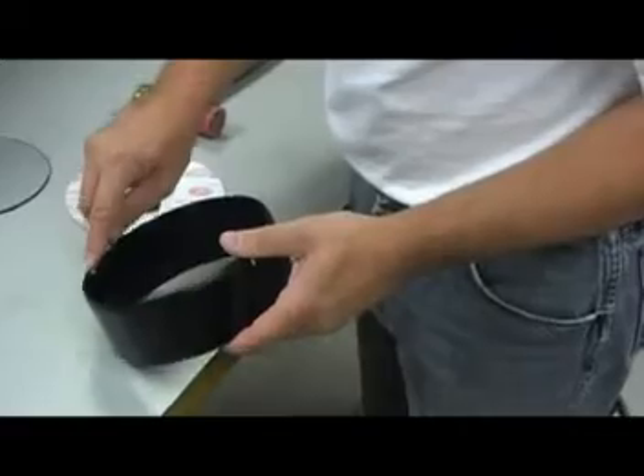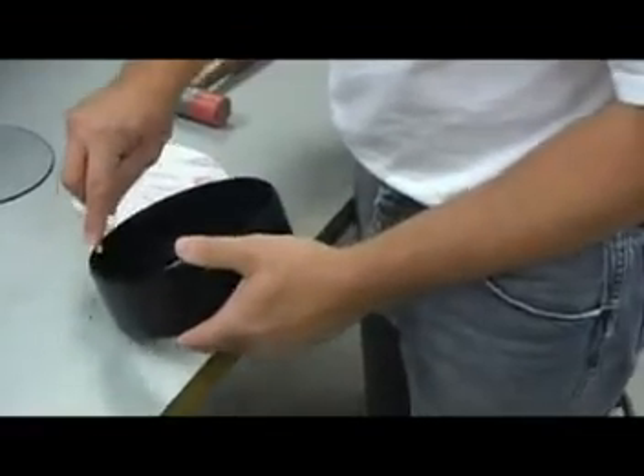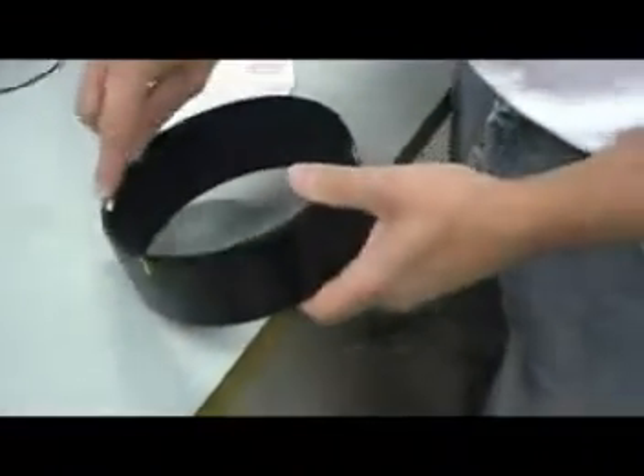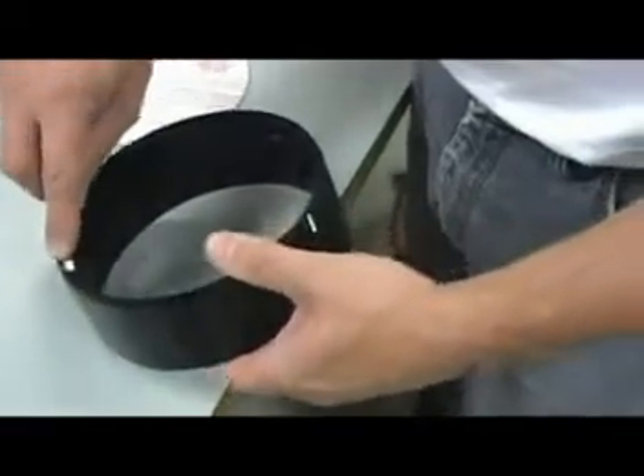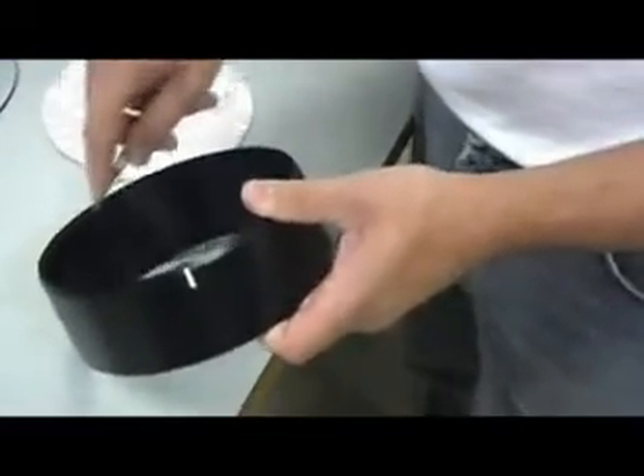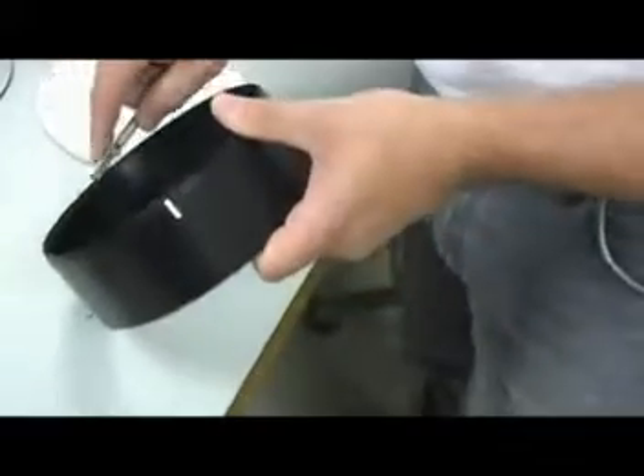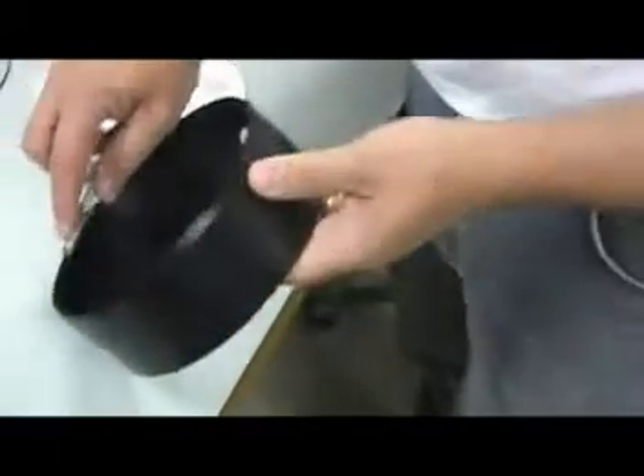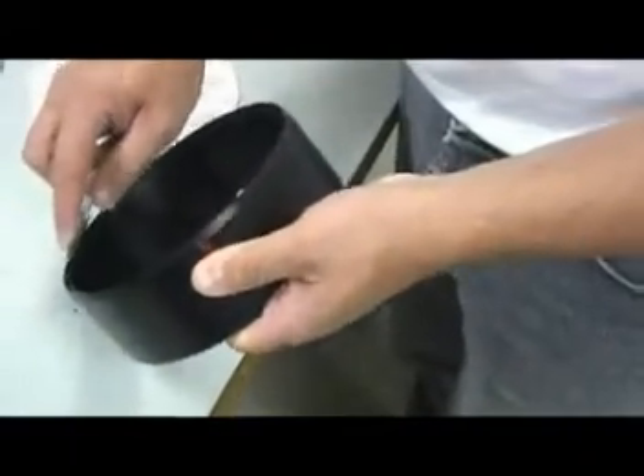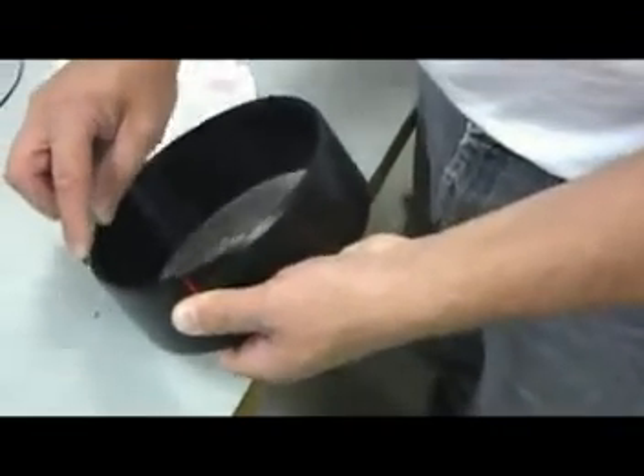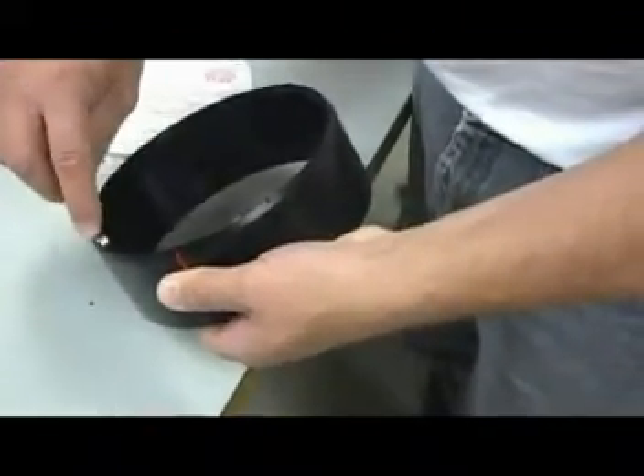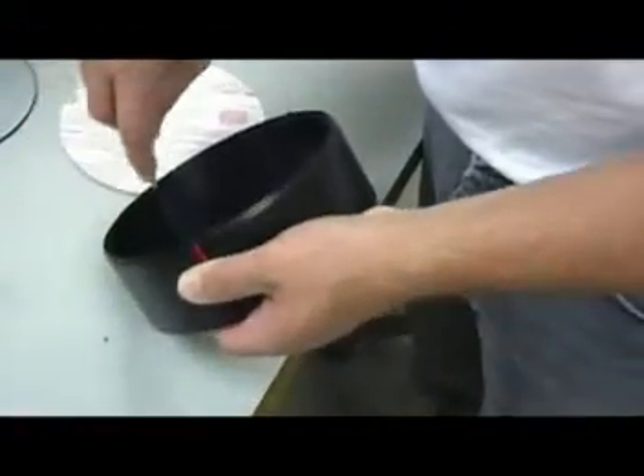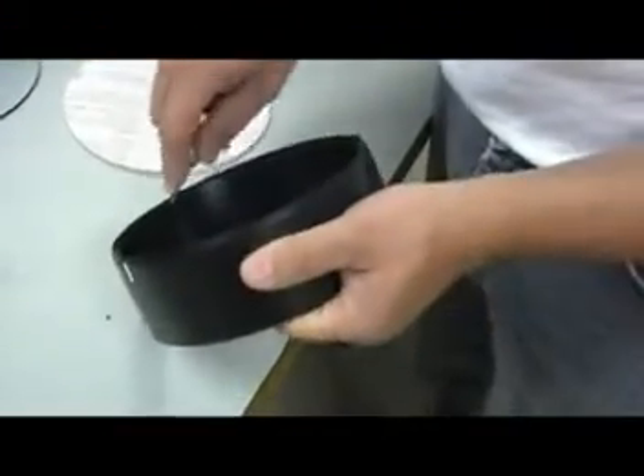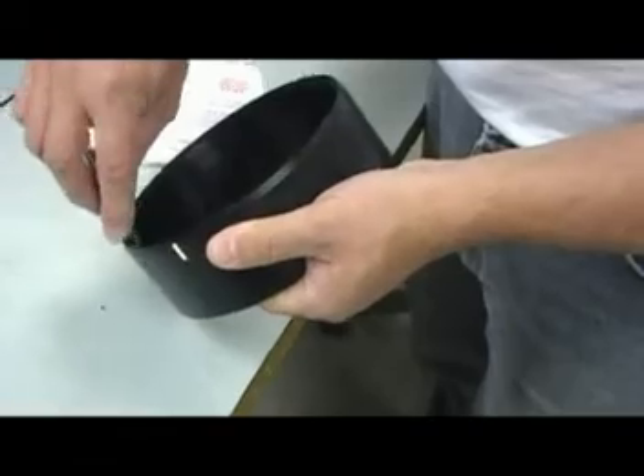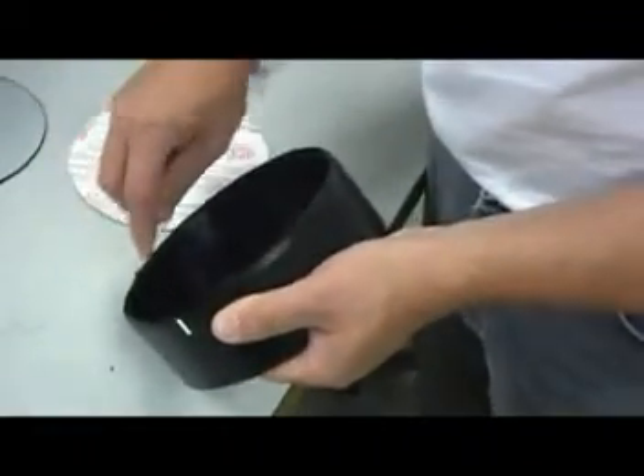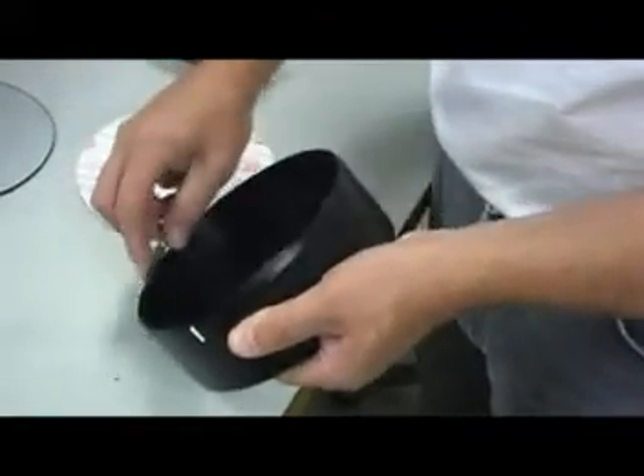Now what we're going to want to do is remove all the old RTV from the sample ring. A razor blade, a small flathead screwdriver, a small scraper can be used, but all the old RTV must be completely removed. You need to take your time doing this. The new RTV won't adhere where the old RTV is, so we do have to be careful to make sure we have that groove as clean as possible.